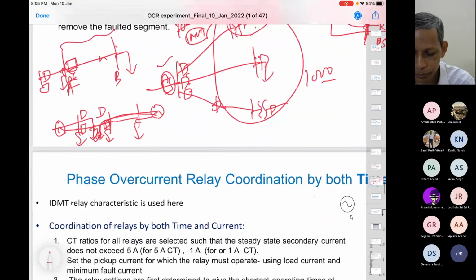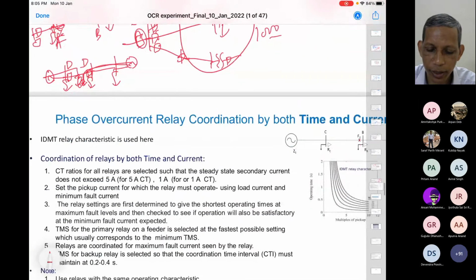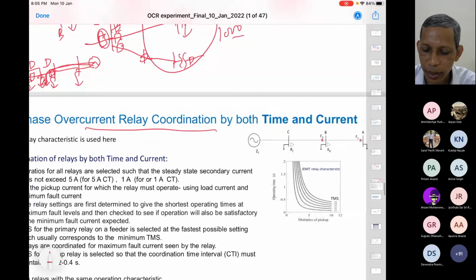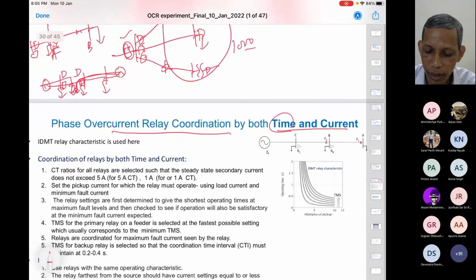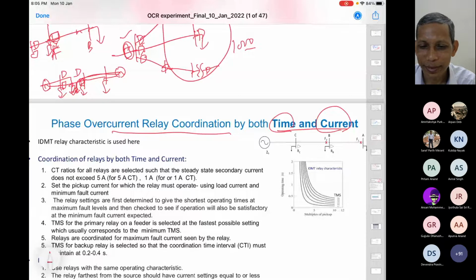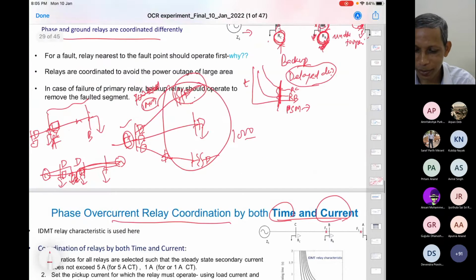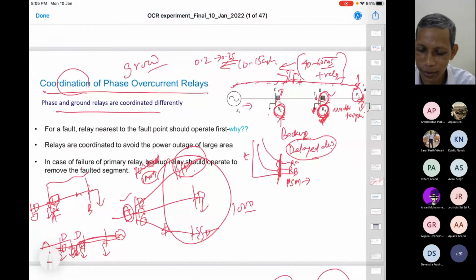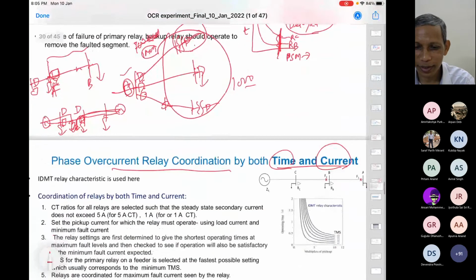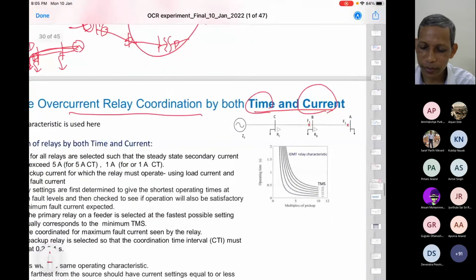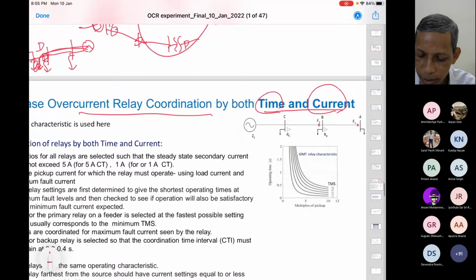Yes, sir. Now phase overcurrent relay coordination, both by time and current. So coordination by both time information and current information. Agree? In the inverse characteristics, we got that because of that reason. We understand now why we require the coordination to have a backup. So see the utility of this curve now. In that case, for an arrangement for a system like this, how can we coordinate RB and RC, that we would like to see.